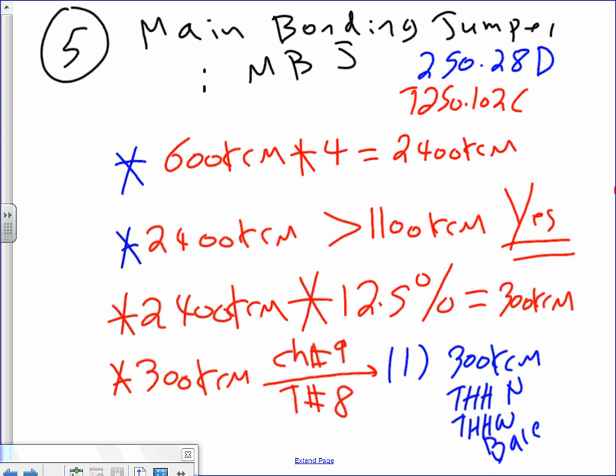So you can have a bare. Now remember, this is a bonding conductor. It's not carrying current. It can be bare. It can be insulated THHN or THHW. Doesn't matter because inside the switch gear is a dry location. Or it could be bare, or it could be covered. Everybody, you guys know the difference between covered and insulated? They look alike. You look at a conductor, it looks like insulated, but they have a cover. The only difference is the thickness of the insulation.